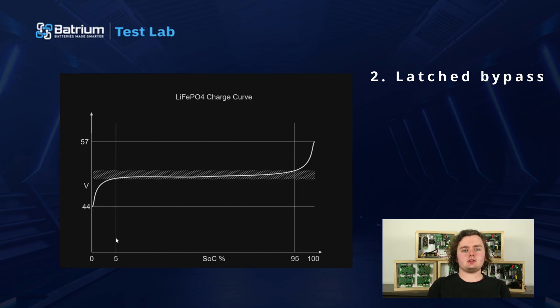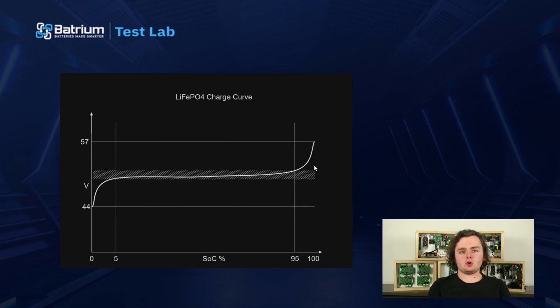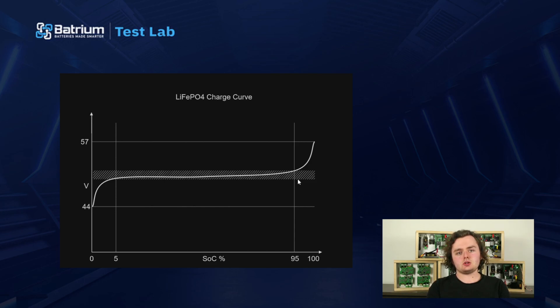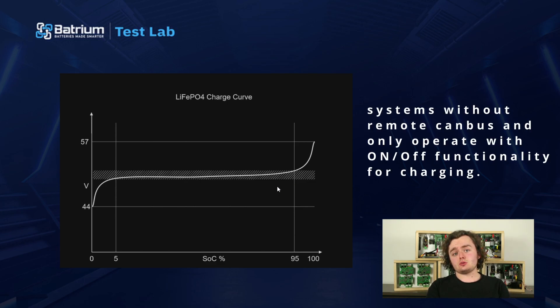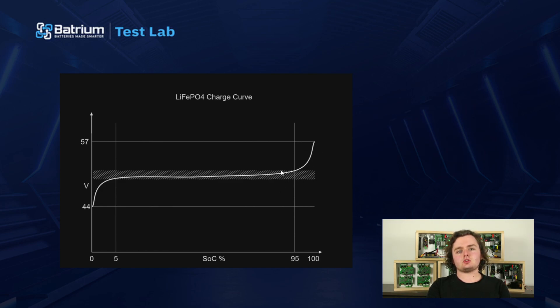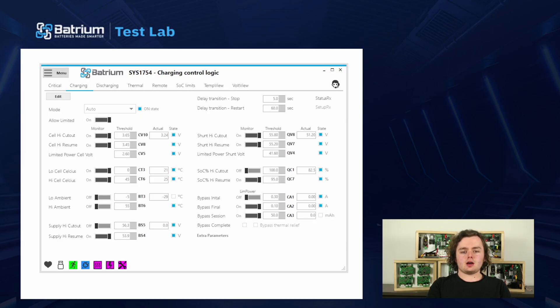That's it for top balancing — on to latch bypass. To explain why this is needed: if you look at the charge curve of lithium iron phosphate, right at the top there's not much energy for the voltage swing. So when top balancing, the cell voltage can drop back down once balancing starts, which then stops the balancing, and the cycle bounces in and out. We saw this pattern in customer systems and introduced latched bypass, where the bypass is latched on for a minimum amount of time after reaching the bypass threshold — regardless of whether voltage drops back under that threshold. This also helps systems without remote CAN control that operate on on/off relay-style charging.